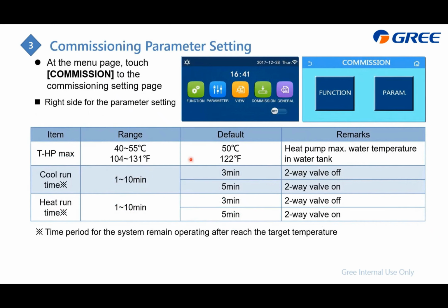This slide displays the detail of the commissioning parameter setting. When you enter this page, it will display this table. You can change these 3, which is the max or the highest water tank temperature for the heat pump, and the cooling run time and heating run time. That means if the temperature reaches the set point, how long the system still operates.